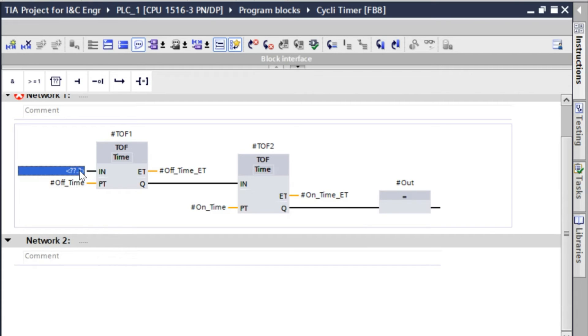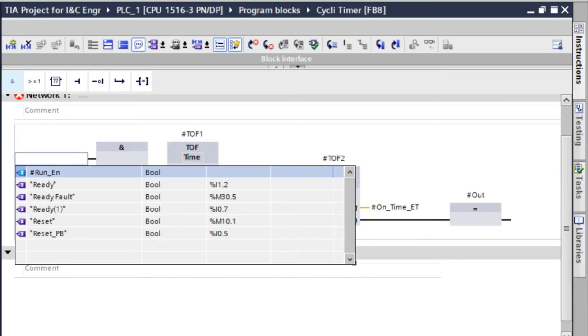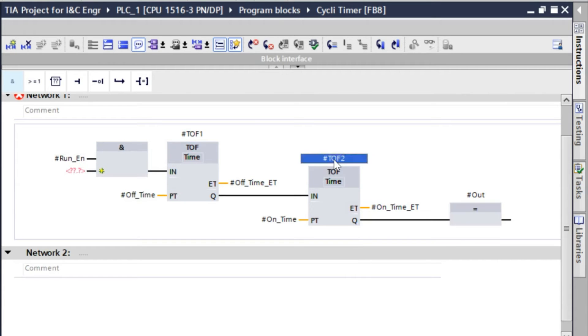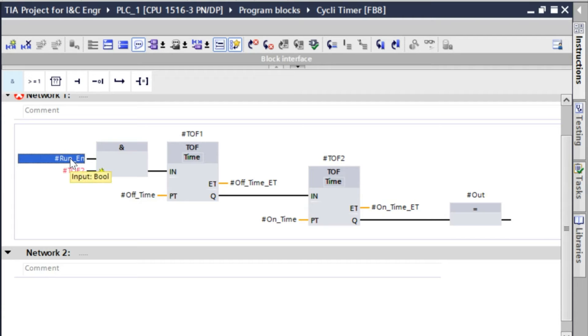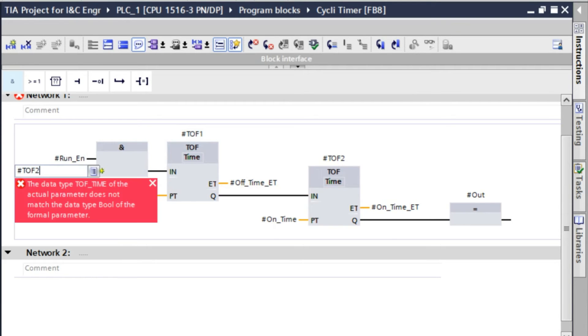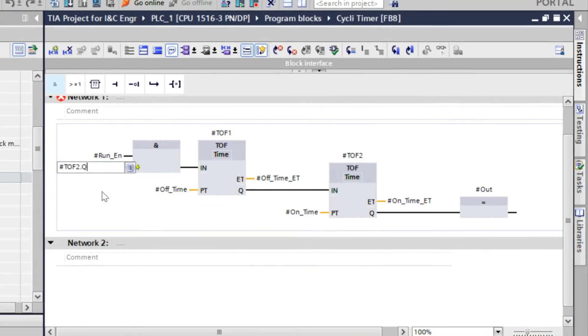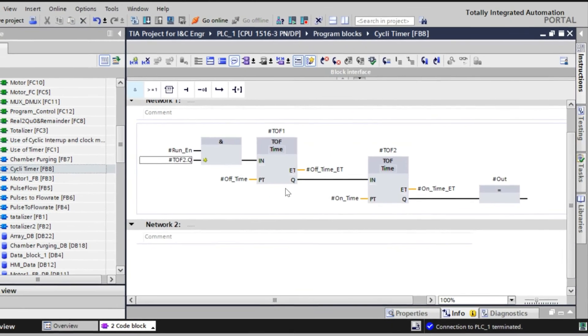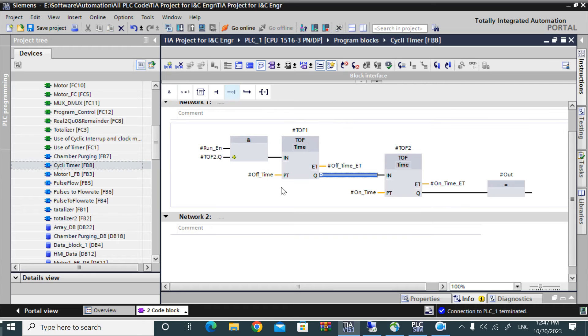Here we have to give a run enable, that run enable. Also we have to give that TOF. For cyclic operation, TON will do the first operation and this TOF will do the cyclic operation. TOF to out. And here we have to give an invert. Now save.